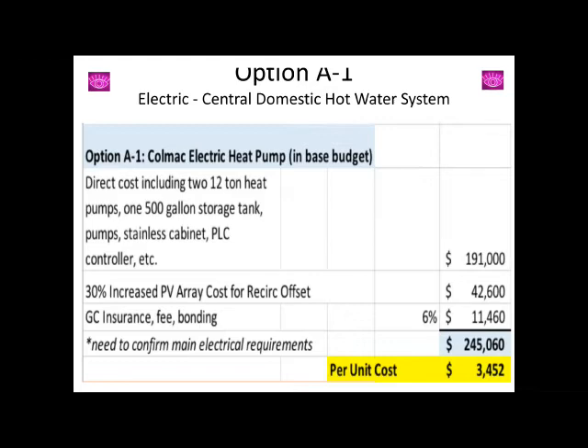As a result, a larger solar array would be needed versus one for decentralized systems. So the increased solar array budget and costs to accommodate the recirculation offset was factored into the cost benefit analysis, causing this to be more expensive than individual water heaters. If we had not factored in the added solar costs, this would have been the most affordable option. I encourage developers to keep that in mind when doing these cost benefit analyses.